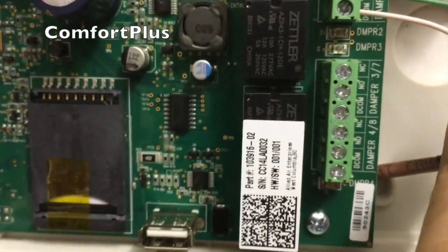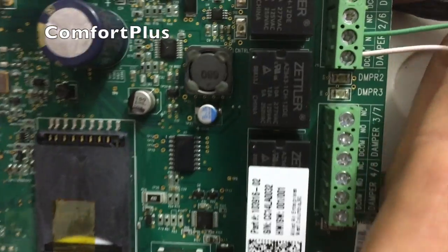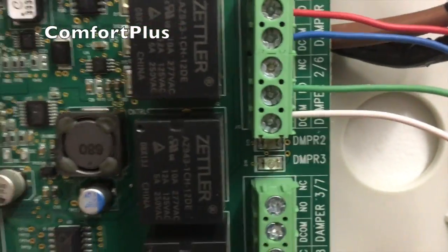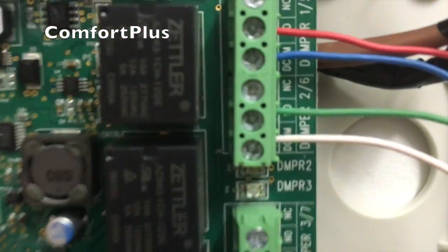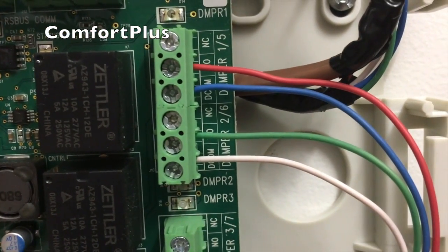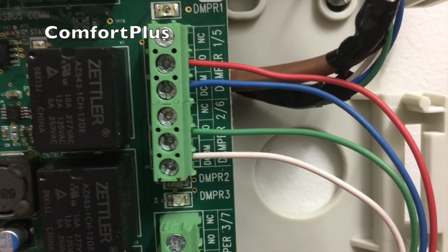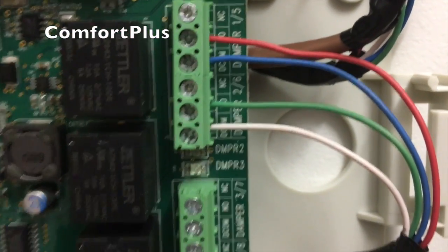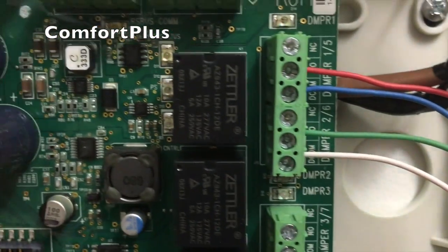Back over on this side, this is where you would hook up your dampers. So I have 2 dampers, zone 1, zone 2. So I'm using one 4-conductor cable, which I'll run to one damper and then jump over to the other damper. They're only about 7 or 8 foot apart. So that's the actual damper connections there.